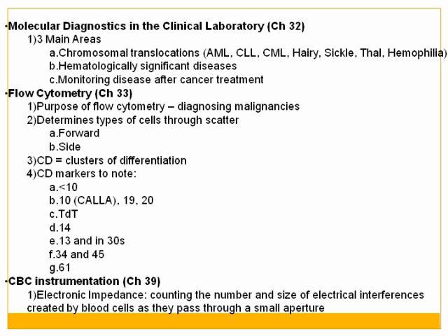Electronic impedance is something that's used in certain analyzers, in how they count the number of cells that are present. So basically, there's going to be a small aperture, a hole, and as the blood streams through there, the cells are going to stream one cell at a time through there, and there's an electrical interference created. And every time a cell goes through that small hole, it's going to pulse. And they basically just count the pulses to decide how many cells are present.